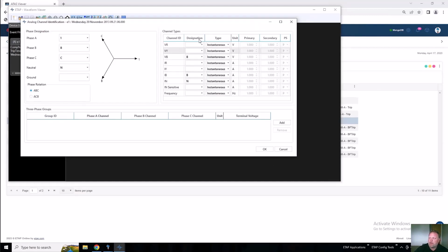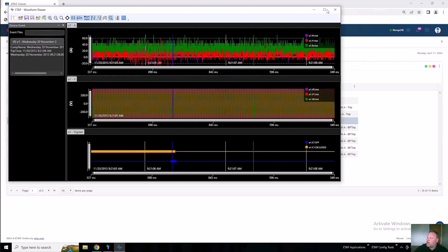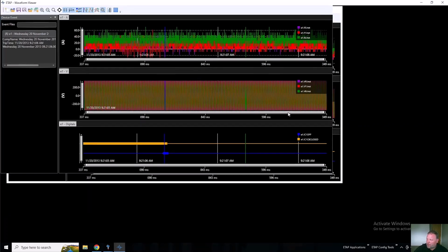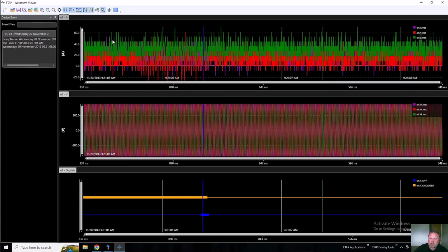We can define what are our phases. We automatically extrapolate what we can from the file itself, but we can actually go in and explicitly define that the value 1 from the ComTrade file itself is my A phase, and we can automatically define, here's my voltages, here's my currents, and so we can very clearly define what we have in the system.